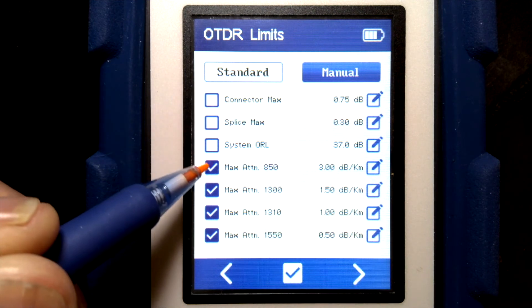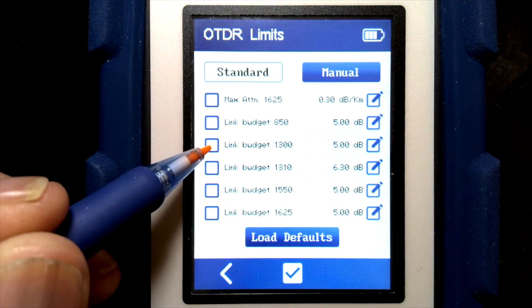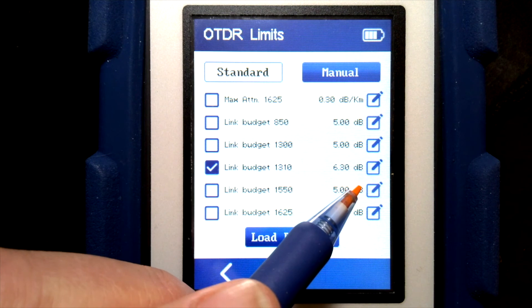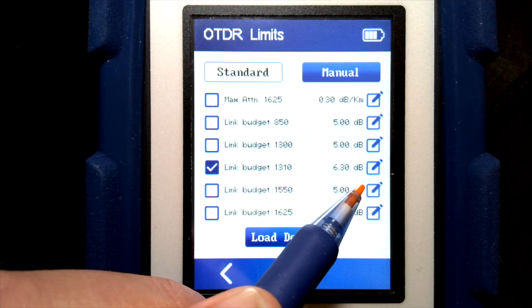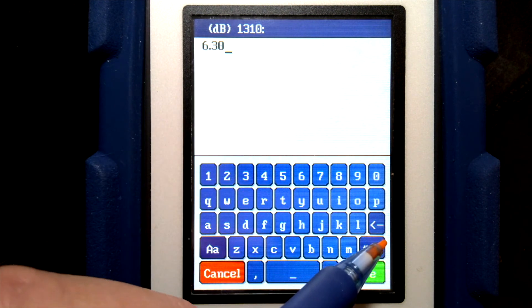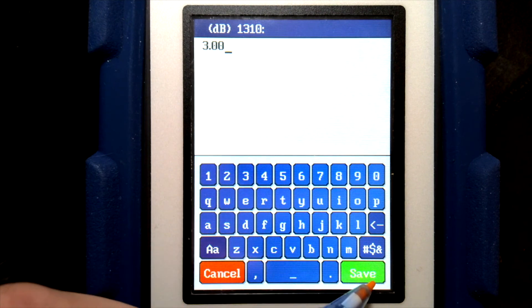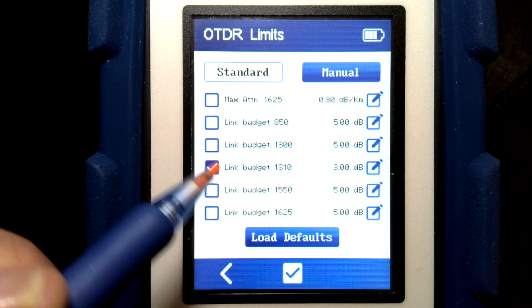For example, if I unchecked all of these and went to the second page and checked link budget 1310 — which is a single mode one — it's set to 6.3 dB. So right now it would only fail if the total link loss is over 6.3 dB, ignoring all other parameters. I can edit that and change it down to maybe 3 dB, and now it will fail only if the loss of the link exceeds 3 dB, ignoring connector and splice losses. I can load defaults and it will change these numbers back to the default values.